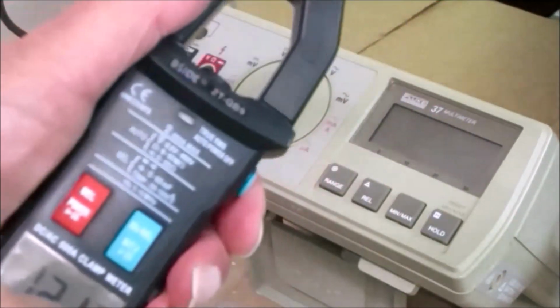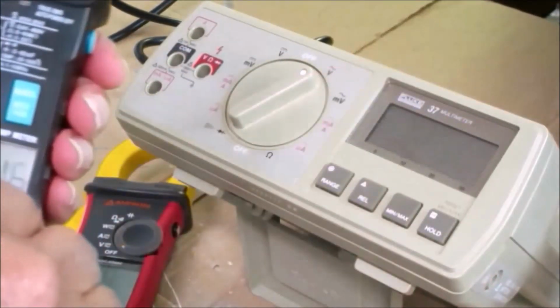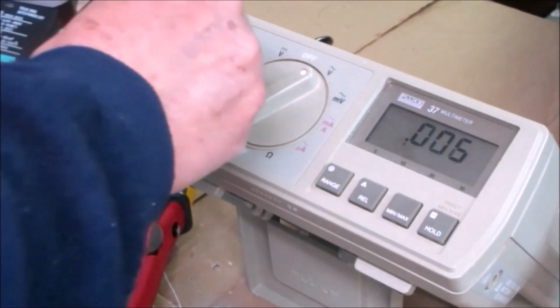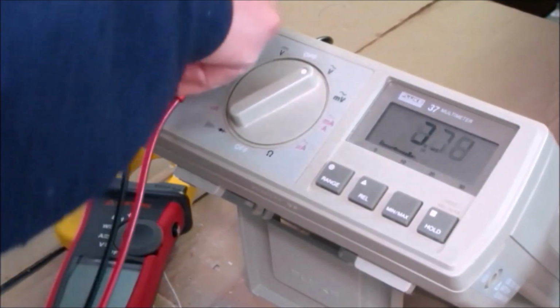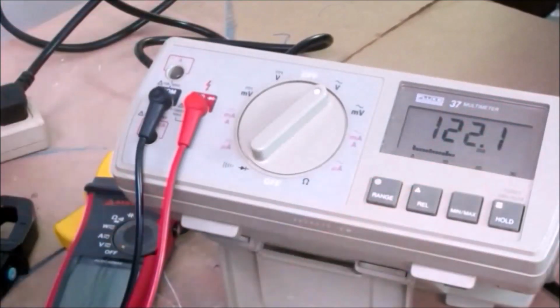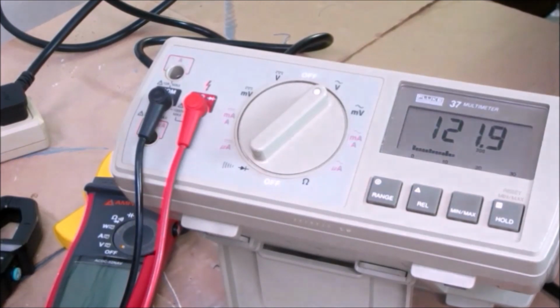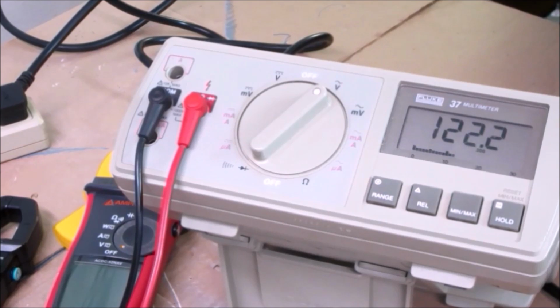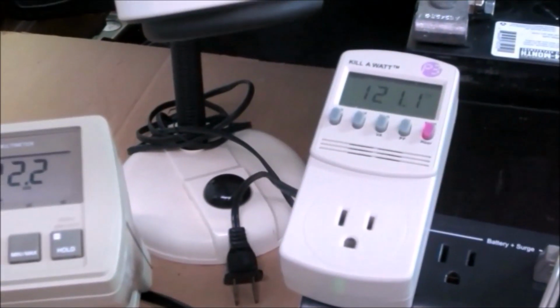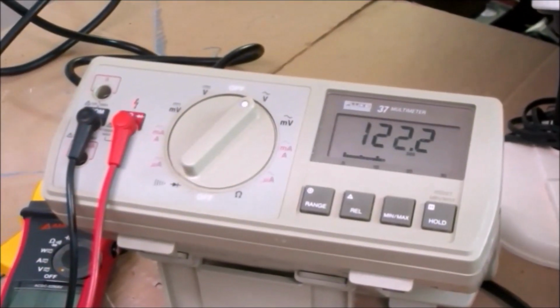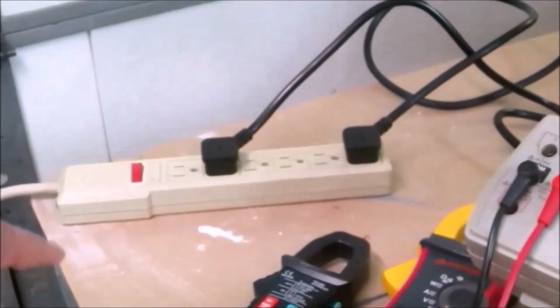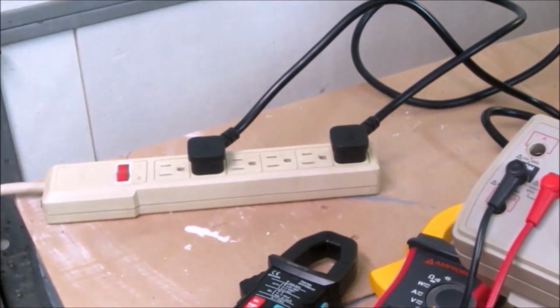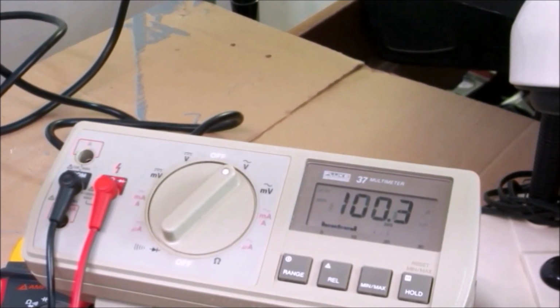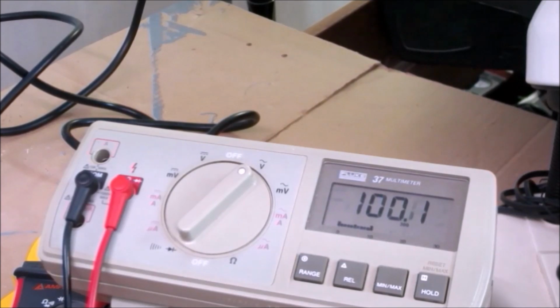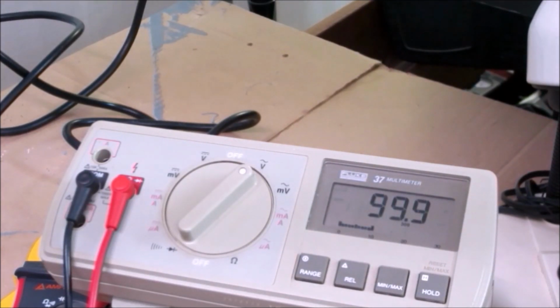So what we're going to do now, I'm going to transfer these leads. You see we're showing 121 line voltage right now. I'm going to transfer these leads to my trusty 40-year-old Fluke 37. Okay, the Fluke 37 showing 122 volts. Kilowatt showing 121. Now watch what happens when I turn off the line voltage. Right here. Fan goes down. Fluke is showing 100 volts. Oh, that's more like it.